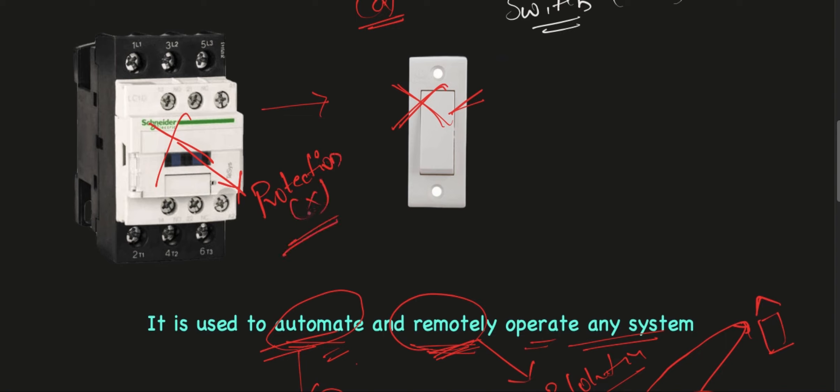Contactor does not provide any protection to the circuit, so we have to use a relay such as overload relay along with a contactor to get protection. Now let's quickly recap what we have learned in this section.